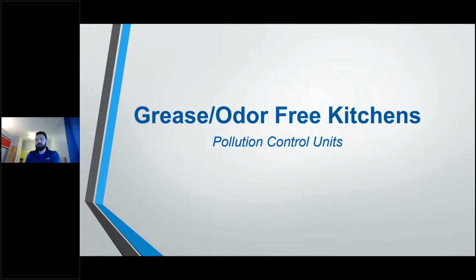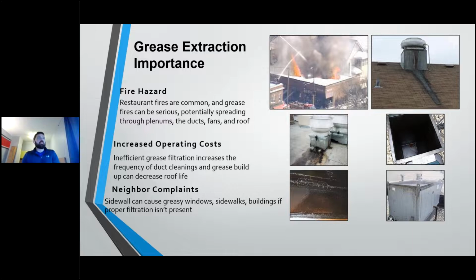So finally, grease extraction importance in kitchens. Grease is a huge fire hazard. Restaurant fires are common, and grease can be a serious problem. Increased operating costs come from grease. You can see, even when you have an up-blast exhaust fan on these things, you can get grease buildup on your deck line or on your roof line. And if you have poor filtration at the hood, that's going to lead to higher duct cleaning costs long term. So what do we do to combat this in the kitchen ventilation systems space? A couple of different things.